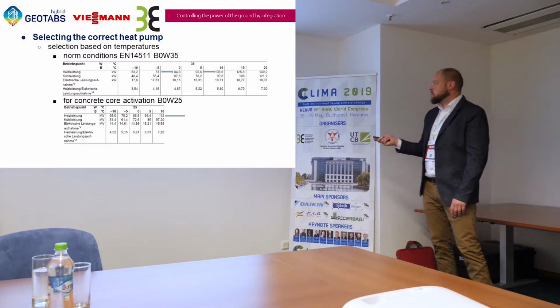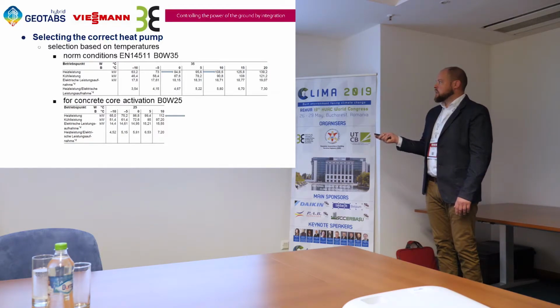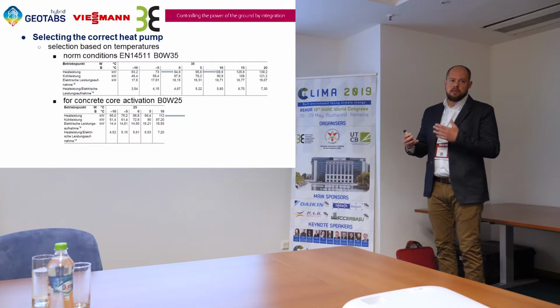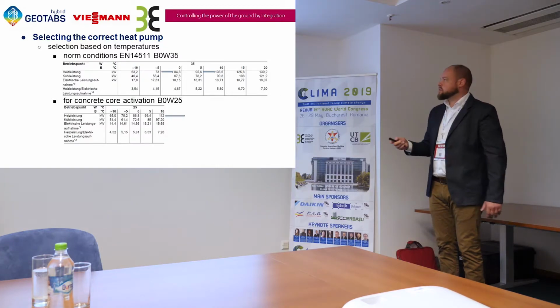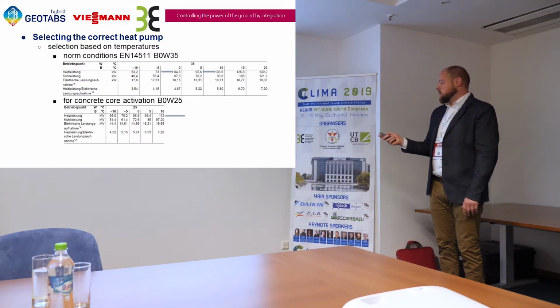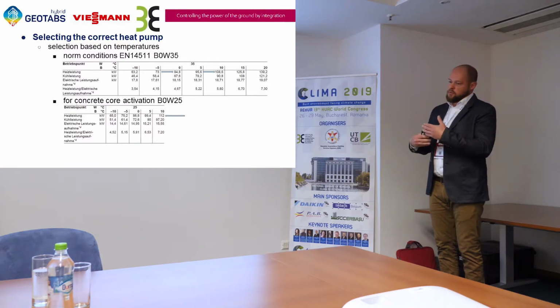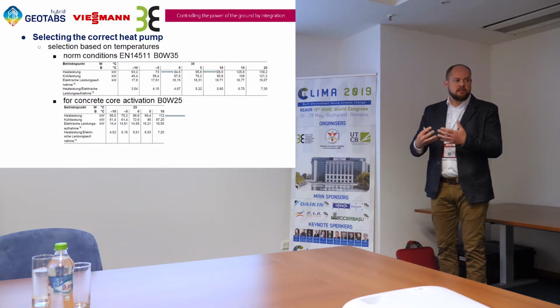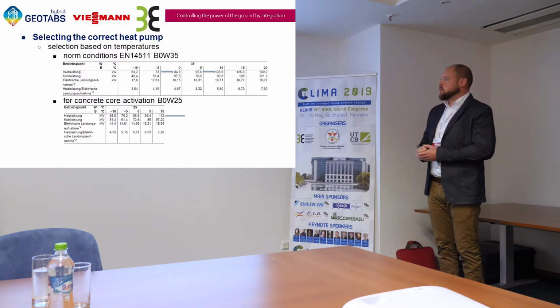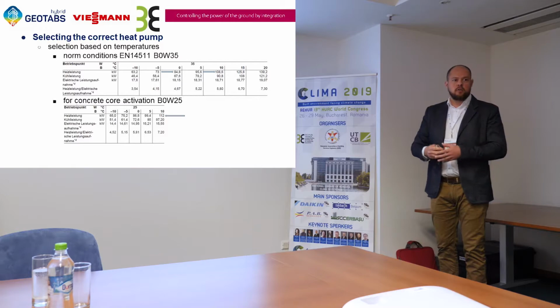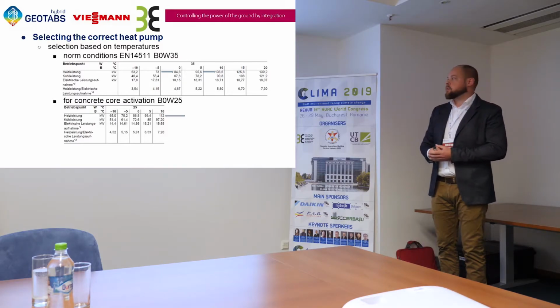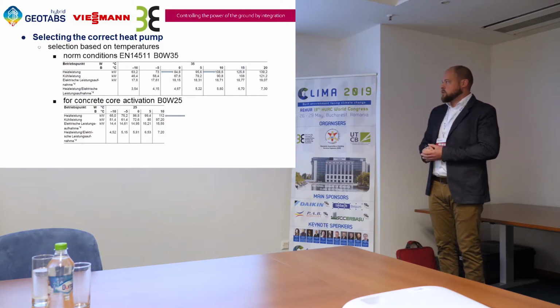degrees. You can see here that the output power of the heat pump changes also, but that means also that the cooling power on the primary side, on the evaporator side, also changes. And the COP goes up. So when the COP goes up, we actually use more energy from the source than at the norm conditions. So that is very important to know on which condition the heat pump is going to run, to know exactly how much power I am going to use from the source.